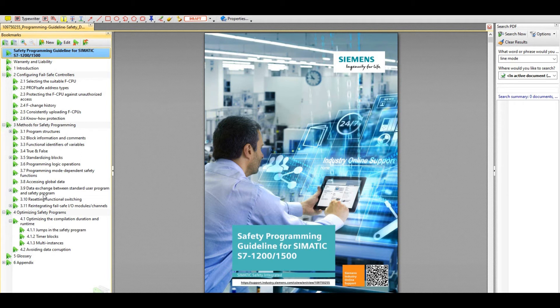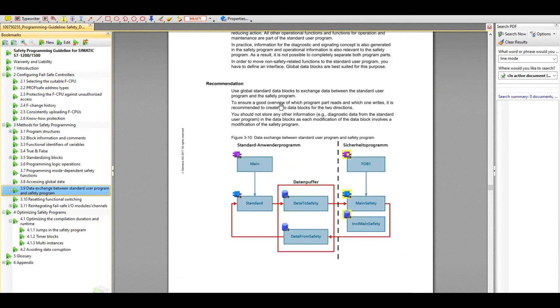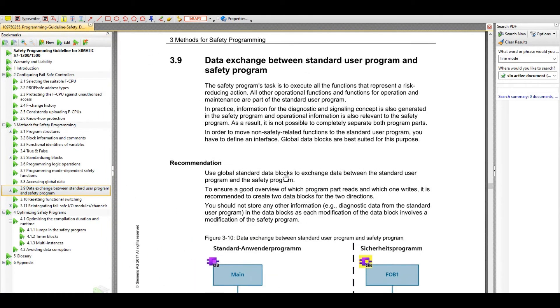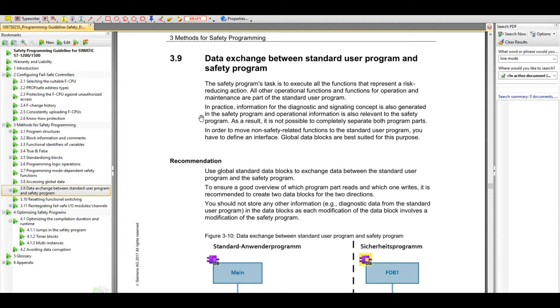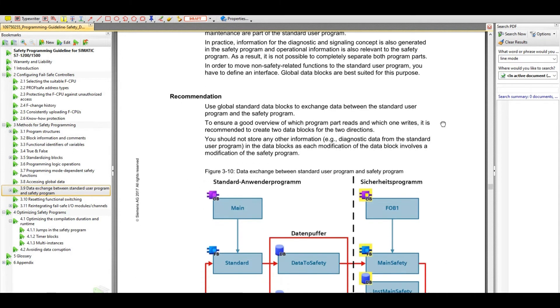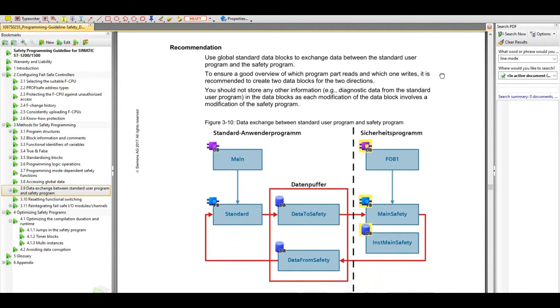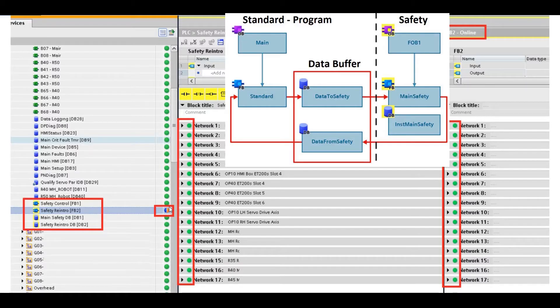If we go to section 3.9, this talks about the data exchange between the standard user program and safety program. In order to move non-safety-related functions to the standard user program, you have to define an interface. Global data blocks are best suited for this purpose. If you read the detail of this recommendation, the key idea is we need to create one or two interface buffer DB.